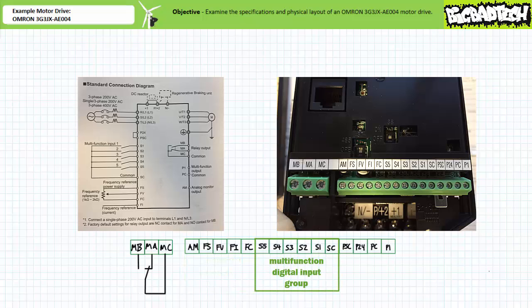The multi-function digital input group consists of five user programmable switched inputs, S1 through S5, as well as a switch common SC shared by all inputs. Depending upon how the motor drive is programmed, these inputs can be assigned different functions, like forward or reverse.